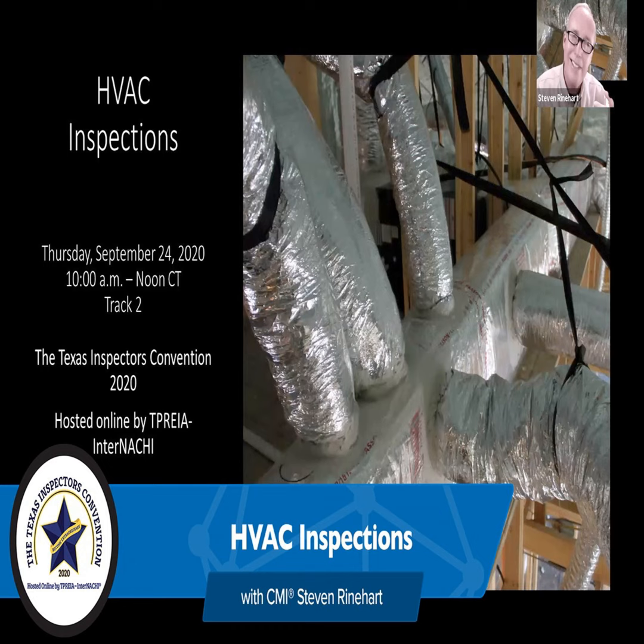So, auxiliary water. Standards say if you see water in a secondary pan, actually it says primary and secondary. I don't know if even primary pans, but secondary pan, you see water, it's a defect. They have gone further to say if you see evidence of water, it's a defect.